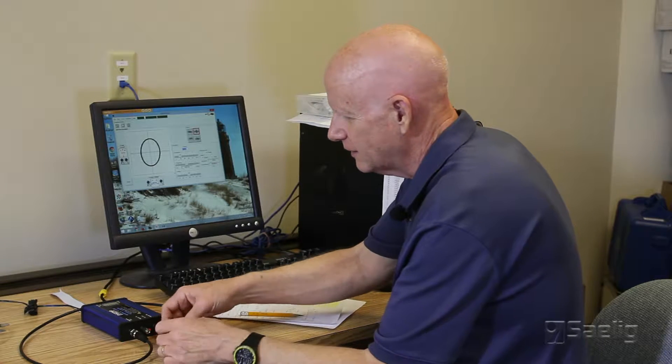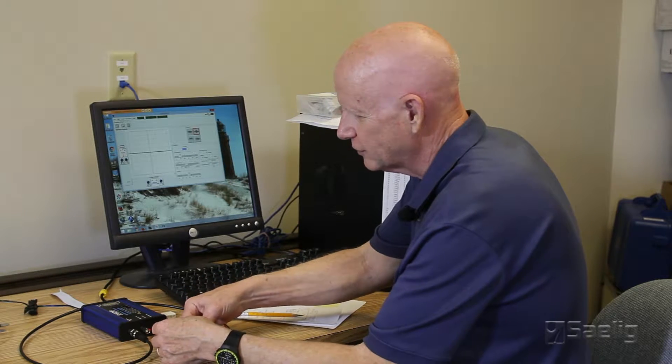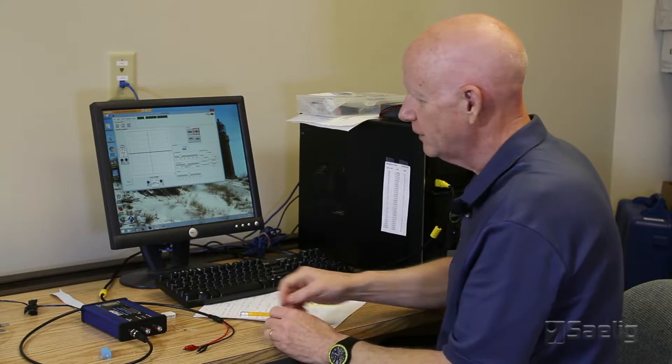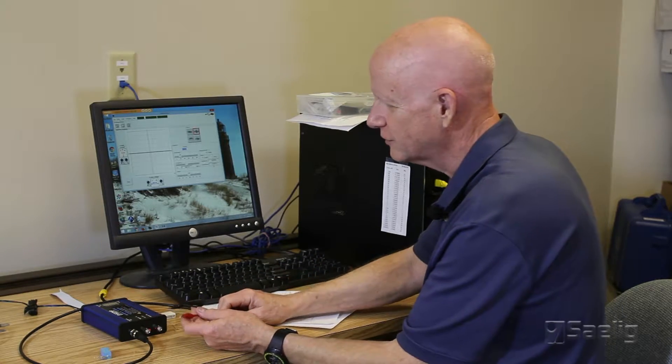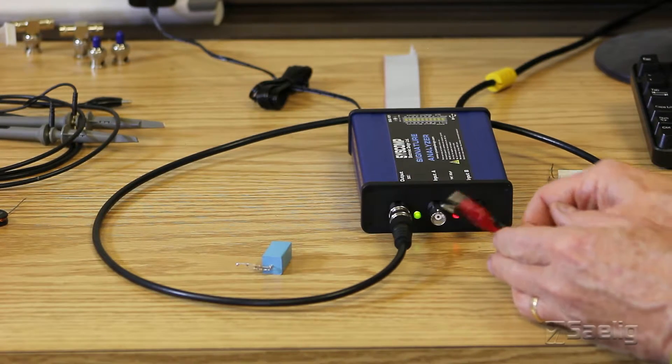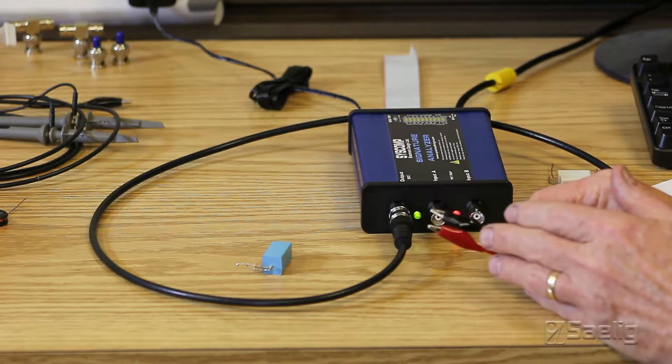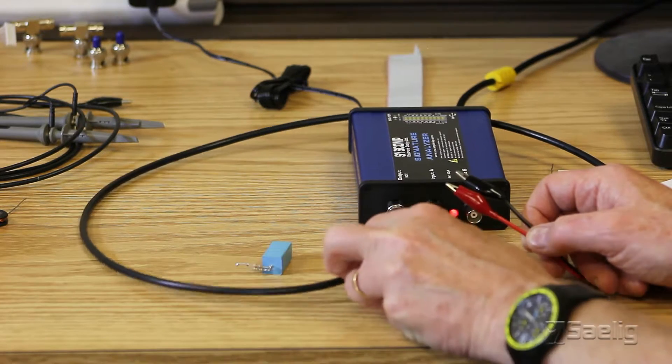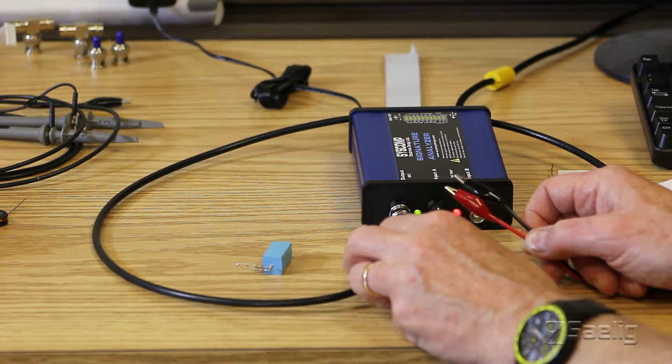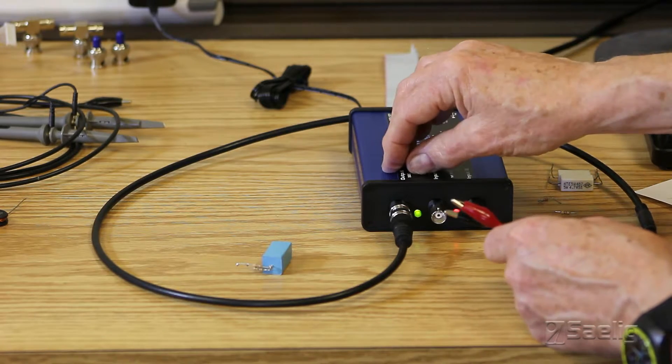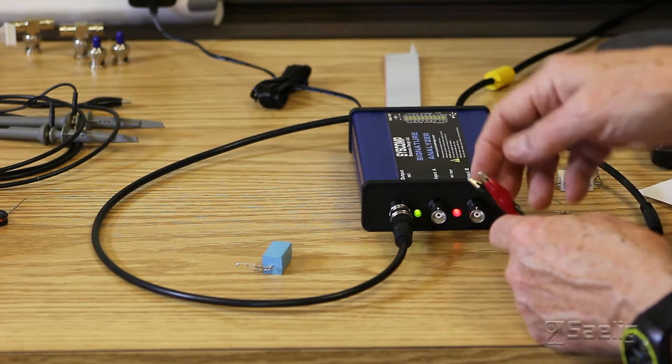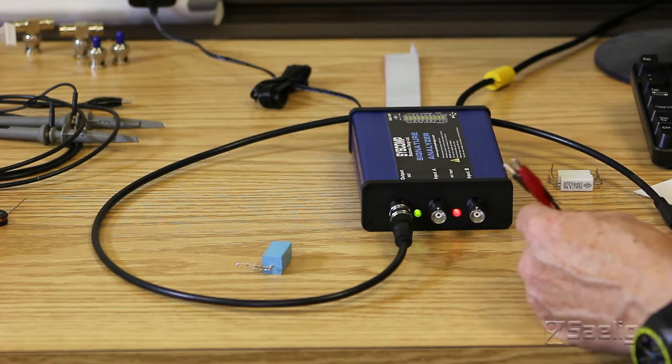Unfortunately, I don't have any raw inductors that I can make available right now, so we're going to have to skip that part. But one of the things that I should have mentioned right at the beginning is that when you're using the signature analyzer, what you use is just the output from the generator itself. It has some circuitry in here that it's making measurements from when it gets into this mode.